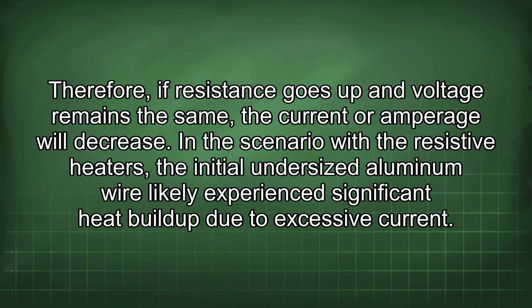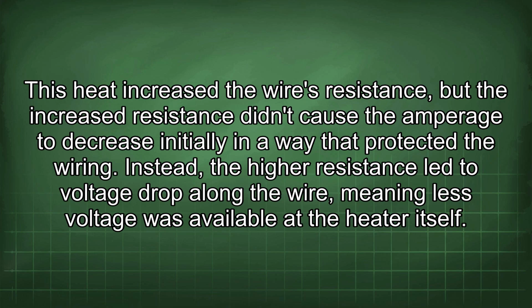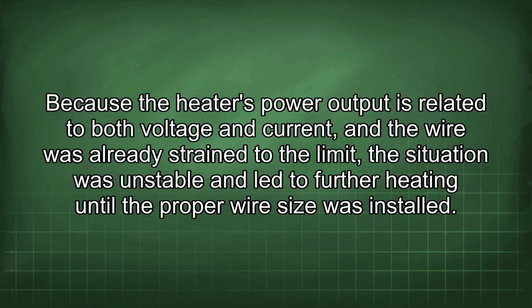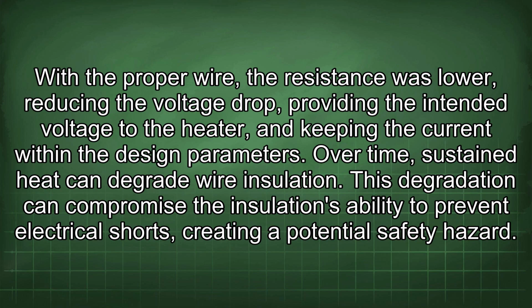In this scenario, with the resistive heaters, the initial undersized aluminum wire likely experienced significant heat buildup due to excessive current. This heat increased the wire's resistance, but the increased resistance didn't cause the amperage to decrease initially in a way that protected the wiring. Instead, the higher resistance led to voltage drop along the wire, meaning less voltage was available at the heater itself. Because the heater's power output is related to both voltage and current, and the wire was already strained to the limit, the situation was unstable and led to further heating until the proper wire size was installed. With the proper wire, the resistance was lower, reducing the voltage drop, providing the intended voltage to the heater, and keeping the current within the design parameters.